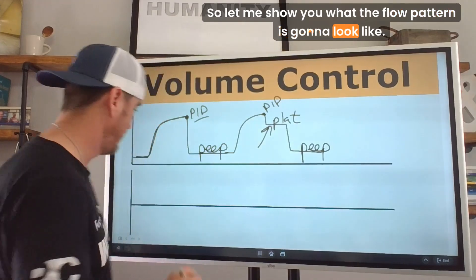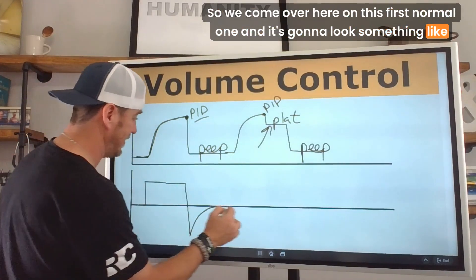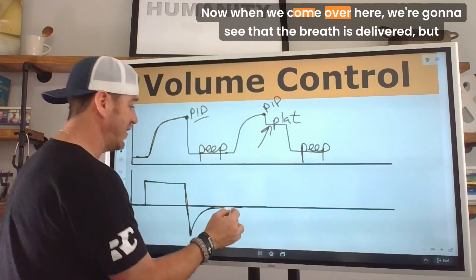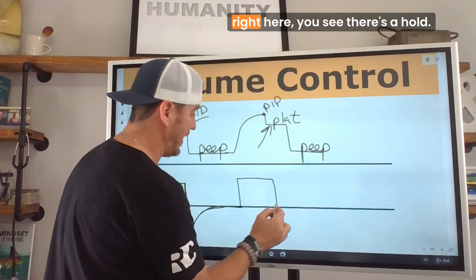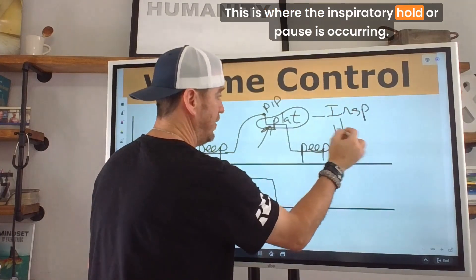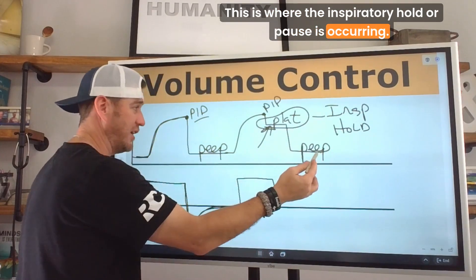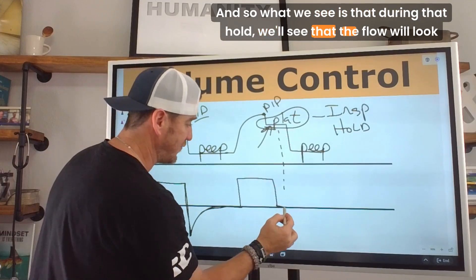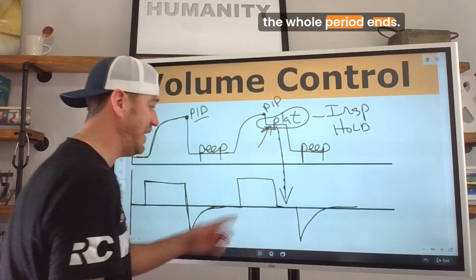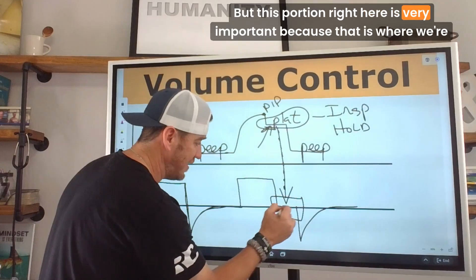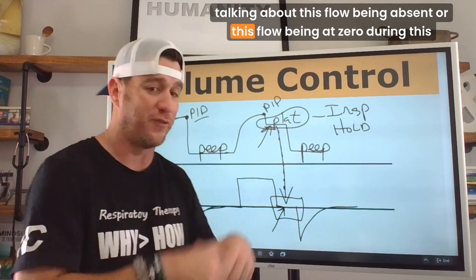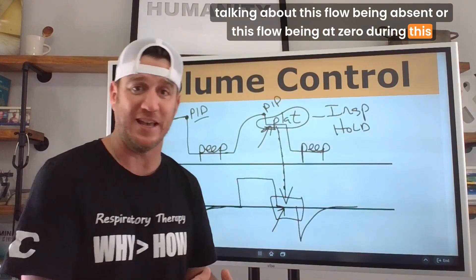Let me show you what the flow pattern looks like. On a normal breath, flow is delivered in a constant flow pattern and then we exhale. When we perform the hold, the breath is delivered and then right here you can see there's a hold occurring — the inspiratory hold or pause. During that hold, the flow will go to zero, and then exhalation happens when the hold period ends. This portion where flow is absent is critical to the assessment of plateau pressure.